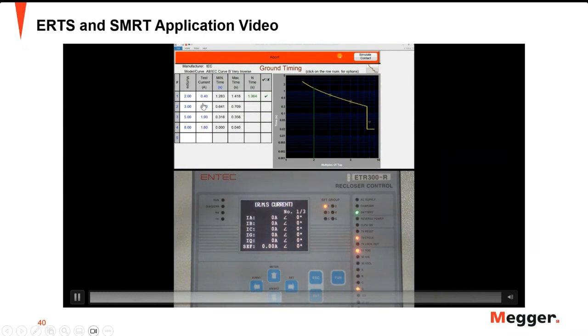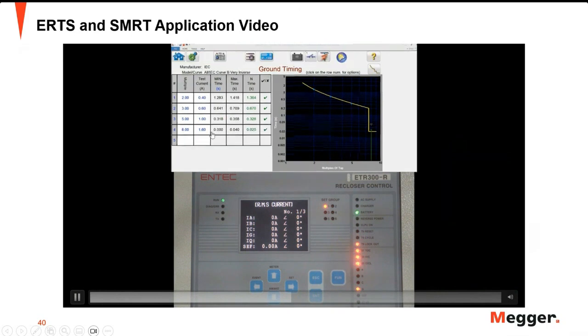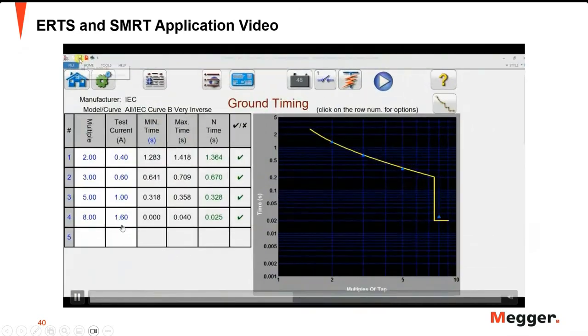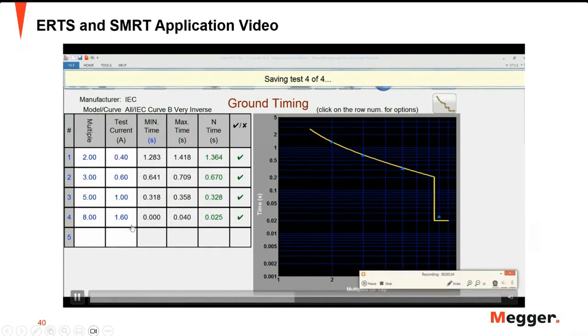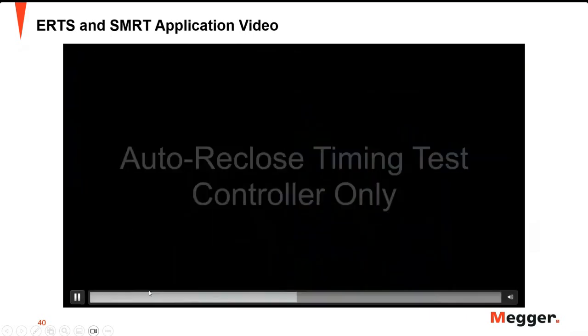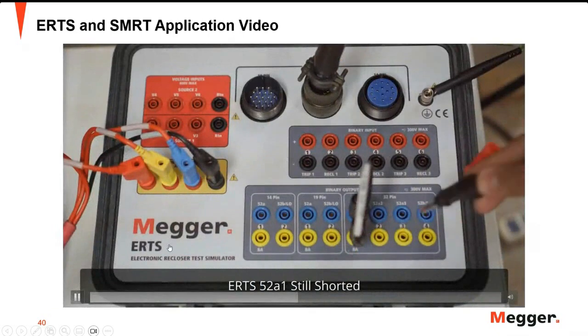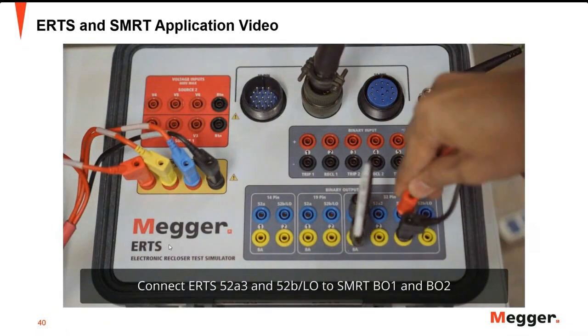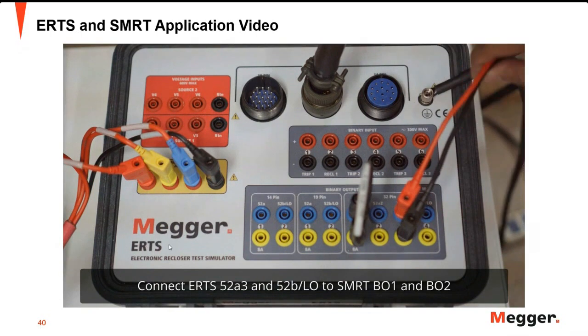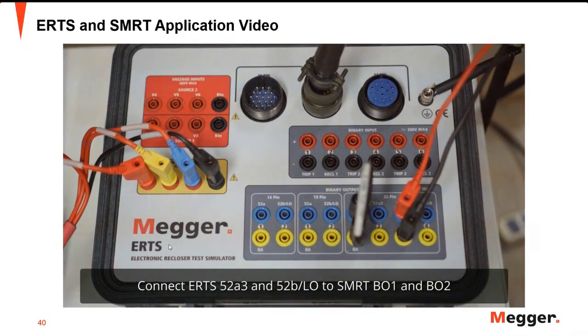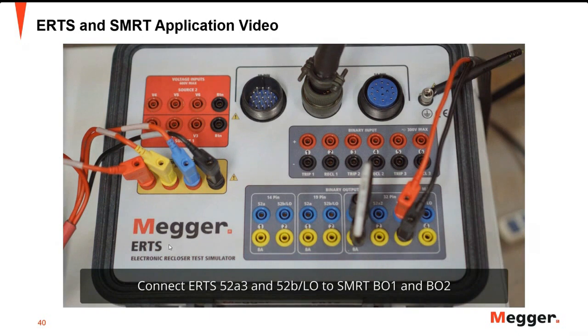The settings for the phase-to-ground element is 0.2 ampere in secondary. The current multiples tested are two times, three times, five times, and eight times — so eight times 0.2 gives you the test current. Now we will do the test for the controller auto-reclosing time.